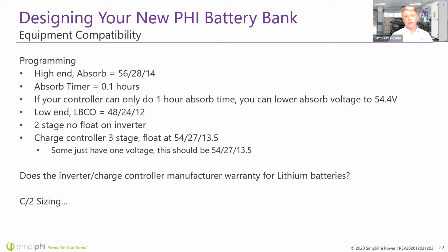However, I know some of the older controllers that are built for lead acid batteries only have an absorb time of 1 hour. So if that's the case for you, you can absorb at 54.4 volts and for 1 hour. It's not going to be as fast of a charge, but it will get the job done if that's all you got. And on the low end, this is the other essential setting, is low battery cutout. This should be able to be set at a minimum of 48 volts. We really recommend 50 for the longest lifespan, but 48 volts is still acceptable and often used on backup systems that aren't used daily.